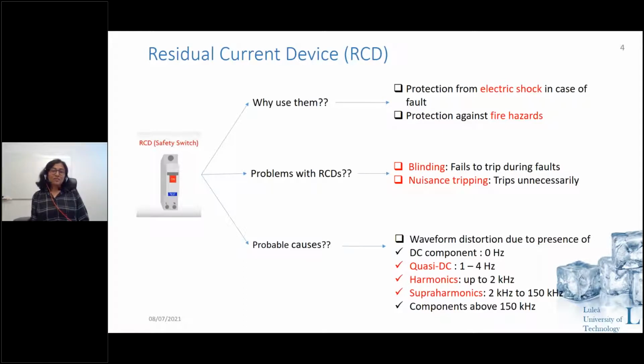Another use of RCD is also for protection against fire hazards in industrial networks, in industrial places where you have dust and oil. If there is an insulation failure in those cases, a current as low as 300 milliamps can also lead to fire. So RCDs are also used for protection against fire hazards.